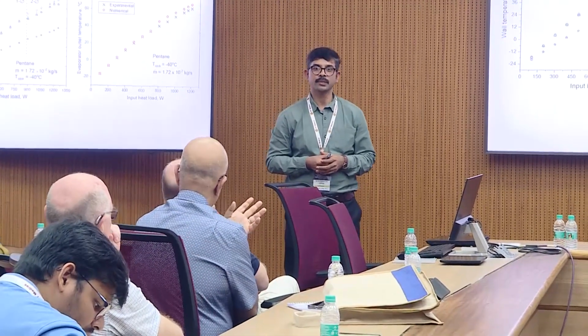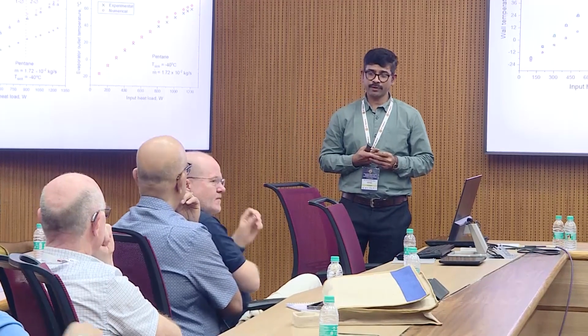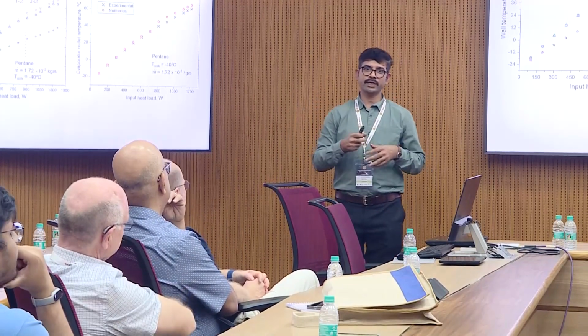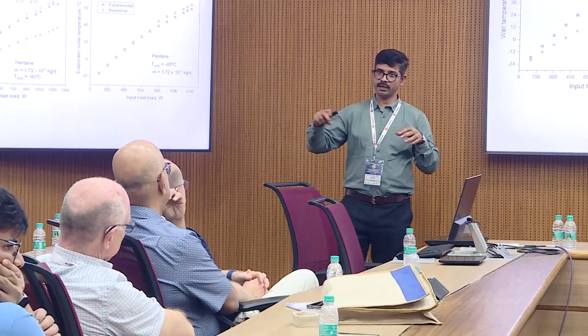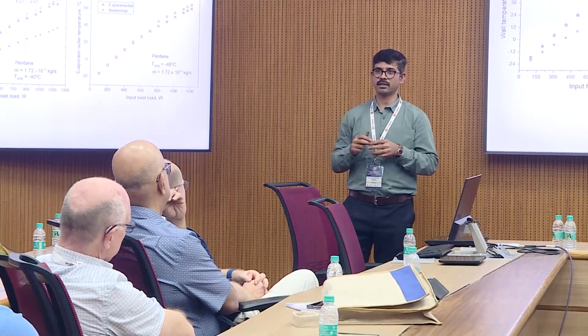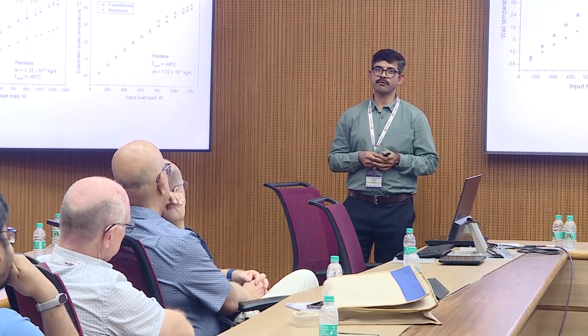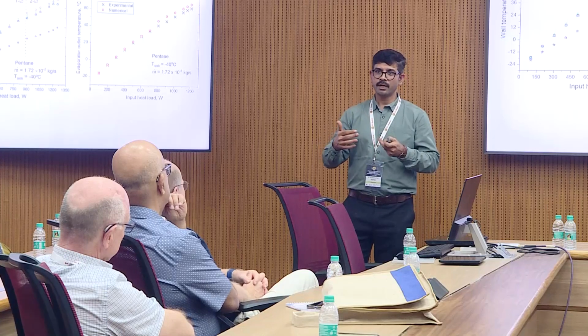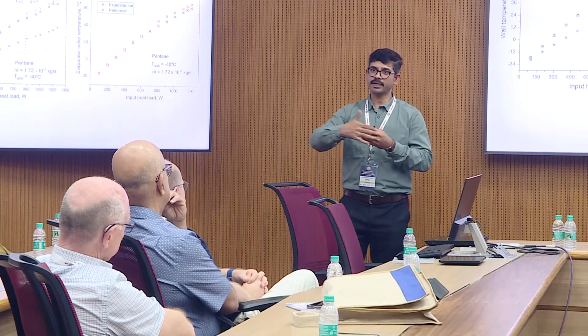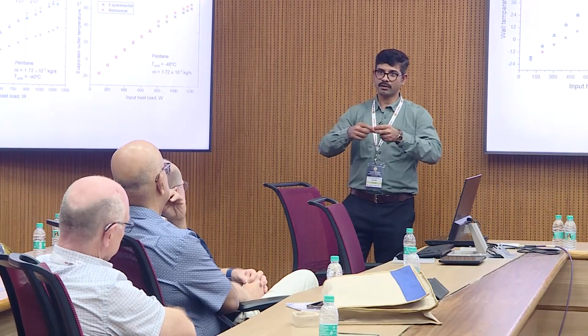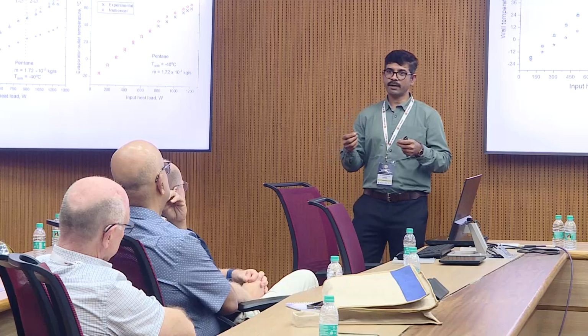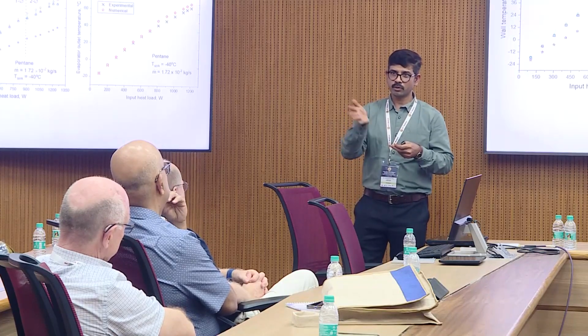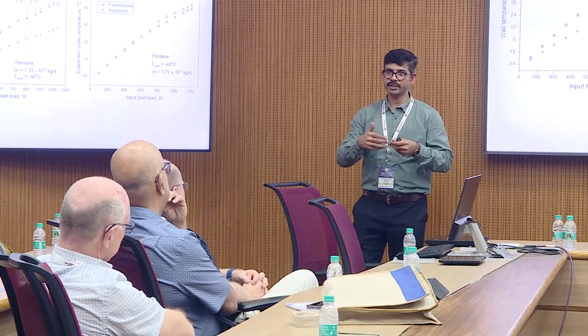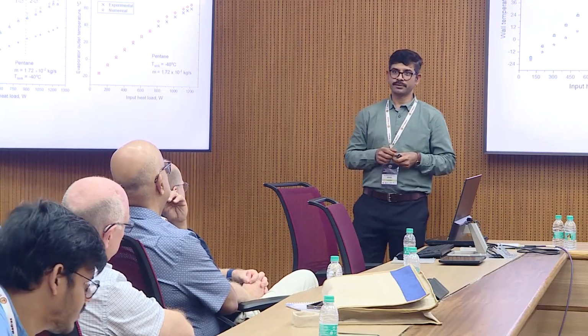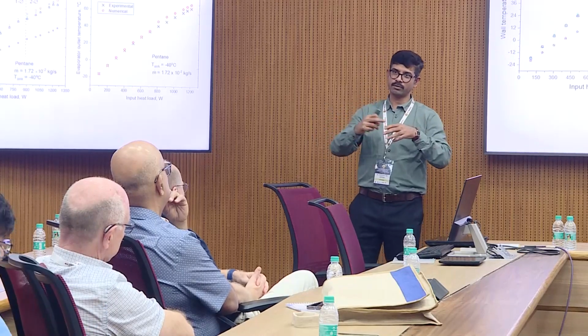Can you say something about whether you get instabilities in your microchannels when you go to higher heat flux? Yes, we have encountered instabilities. Basically, when we initially used straight rectangular or square microchannels, at around 600 or 800 watts, the flow was reversed. Flow reversal happens because of the repeated elongation of the bubbles. So we have cut the microchannels to a zigzag cross section. We have arrested those instabilities and could achieve up to 1 kilowatt. We changed the cross section from rectangular straight to zigzag channels.